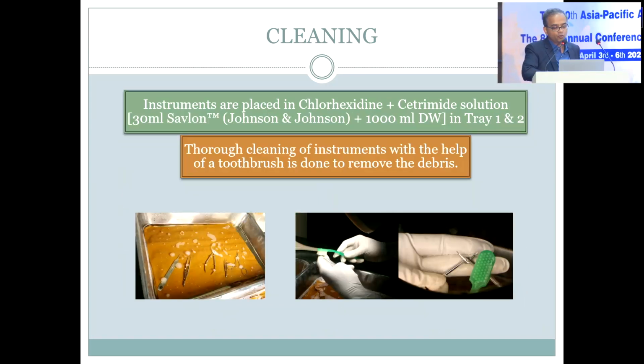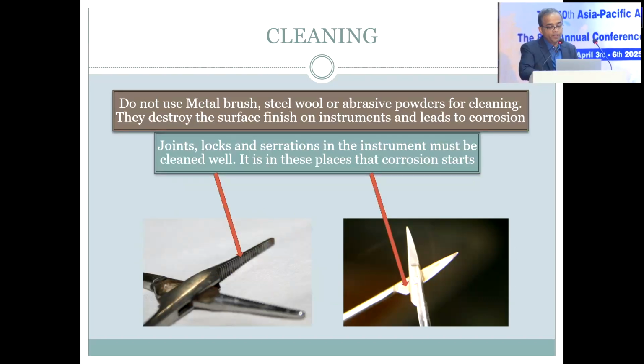Instruments are placed in chlorhexidine and cetrimide solution in trays 1 and 2, and thorough cleaning is done with the help of a toothbrush. So for serrated instruments, we need to clean them with a fine, super soft or soft toothbrush, so that debris can be removed without any damage. The serrations, joints and locks are very important places to be cleaned, because otherwise they get stuck, and those are the places where the debris leads to earlier damage to the instruments, and because these are the places where corrosion will also start.